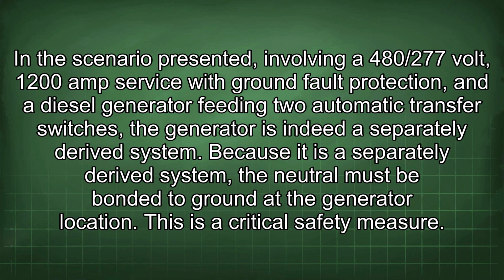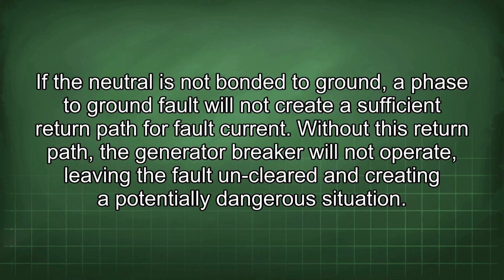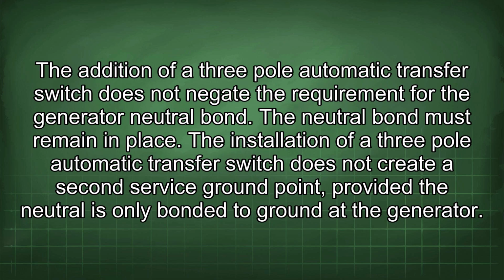Because it is a separately derived system, the neutral must be bonded to ground at the generator location. This is a critical safety measure. If the neutral is not bonded to ground, a phase-to-ground fault will not create a sufficient return path for fault current. Without this return path, the generator breaker will not operate, leaving the fault uncleared and creating a potentially dangerous situation. The addition of a 3-pole automatic transfer switch does not negate the requirement for the generator neutral bond. The neutral bond must remain in place.